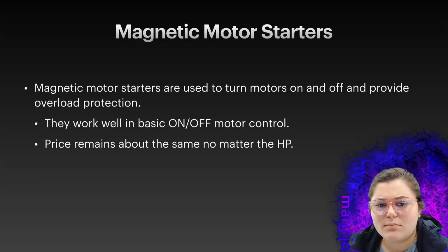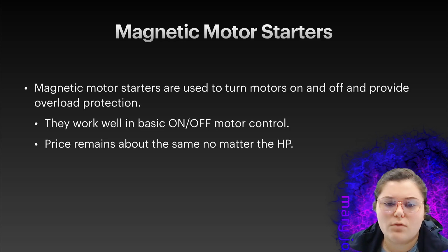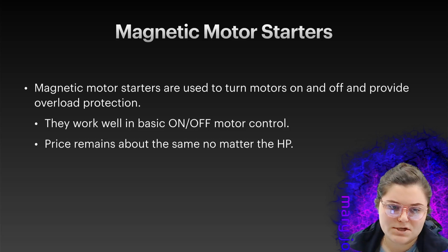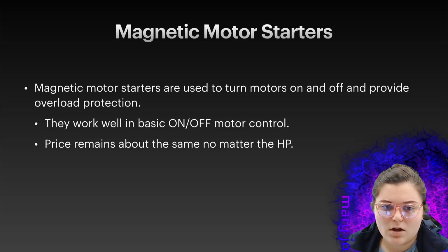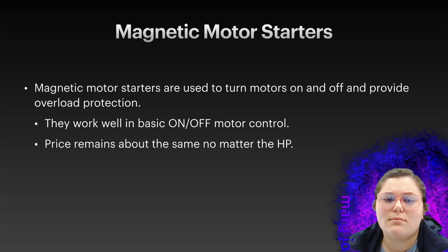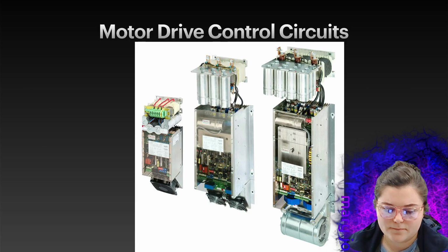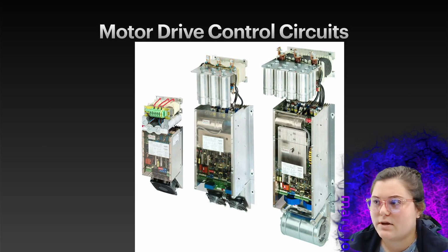Whereas magnetic motor starters, they're used to turn motors off and on, and they provide overload protection. They work well in basic on-off motor control, and the price remains the same no matter the horsepower. So pretty much you're going to be spending the same on a magnetic motor starter, whereas if you start getting on up in horsepower for a motor drive, they can become a little more expensive. So here's just a few pictures of some motor drives.